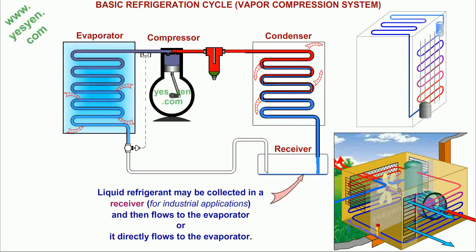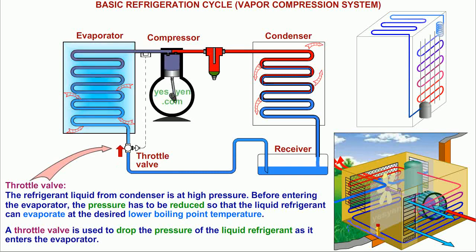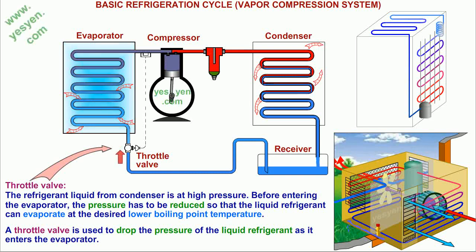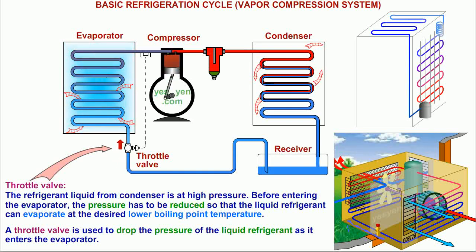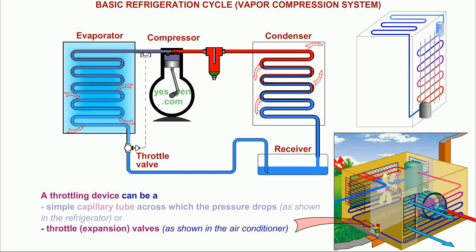Liquid refrigerant may be collected in a receiver and then flows to the evaporator, or it directly flows to the evaporator. Throttle Valve: The refrigerant liquid from the condenser is at high pressure. Before entering the evaporator, the pressure has to be reduced so that the liquid refrigerant can evaporate at the desired lower boiling point temperature. A throttle valve is used to drop the pressure of the liquid refrigerant as it enters the evaporator. A throttling device can be a simple capillary tube across which the pressure drops, as shown in the refrigerator, or a throttle valve as shown in the air conditioner.